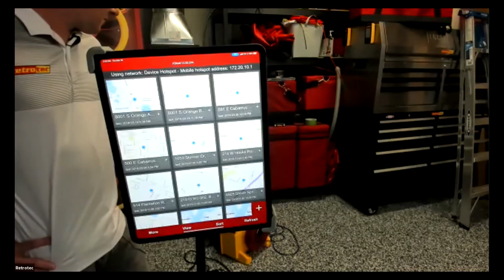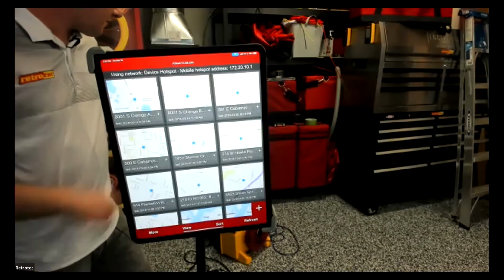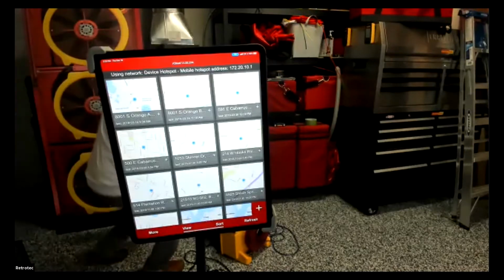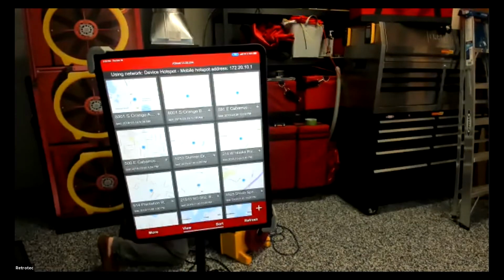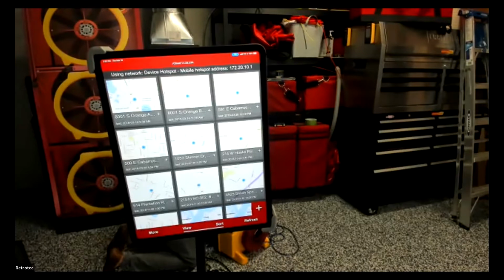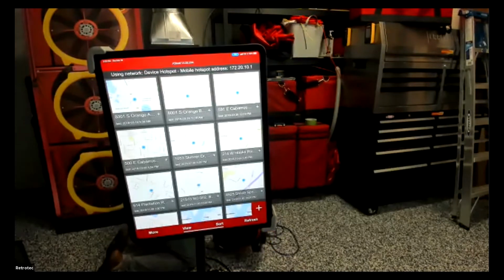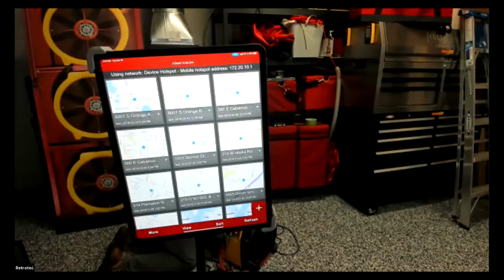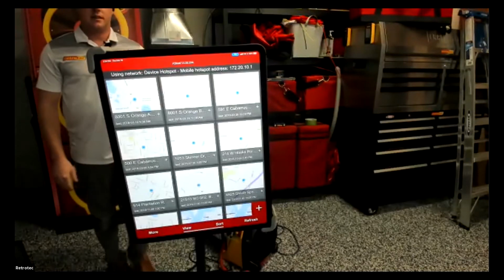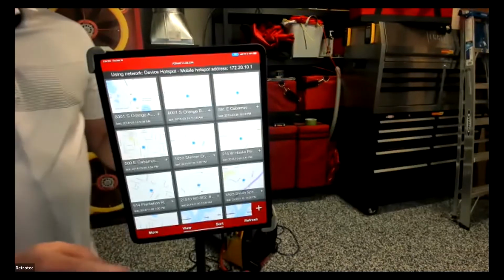Someone was asking if there's a different setting between the 340 and the 300. So if you're doing a duct test versus a blower door, there is. When we're showing the gauge again, maybe we can show that really quick. There are two different device pages, one for blower door, one for duct tester, and they both have the 300 series on them. And the duct tester is always going to be the 340 or the 350. The blower door will always be the 300. That's just a package name we use for those two kits.